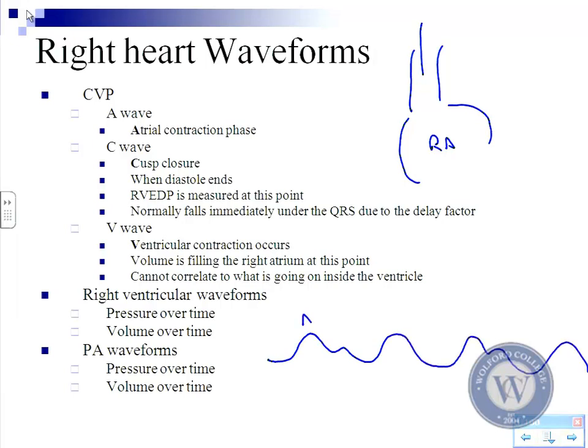Okay, that's your ACV. Now, of course, if you just measure it by taking your measurement and going down to a really low amplitude, you'll see this, which is what a lot of you are accustomed to. I would recommend that you don't do that. Do not have your pressures at 120. Make sure you have your pressures at 20 or 30, so you can actually see the waveform.